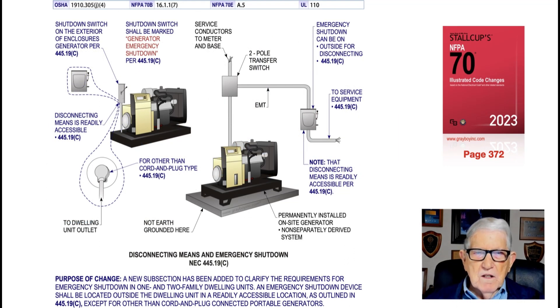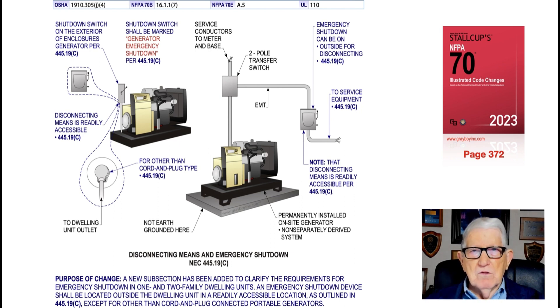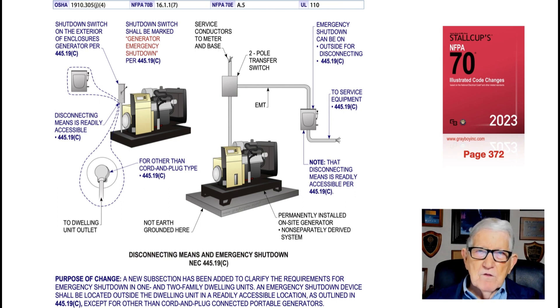This illustration deals with the disconnecting means and emergency shutdown in accordance with 445.19(C), covering a dwelling unit. The purpose of the change states — paraphrasing — that a disconnect switch or a cord-and-plug connection could serve as the disconnect, but an emergency generator shutdown means is still required in accordance with 445.19(C). Read the notes and call-outs in blue and you'll get a very good handle on exactly what this requirement is asking the installer or designer to do.